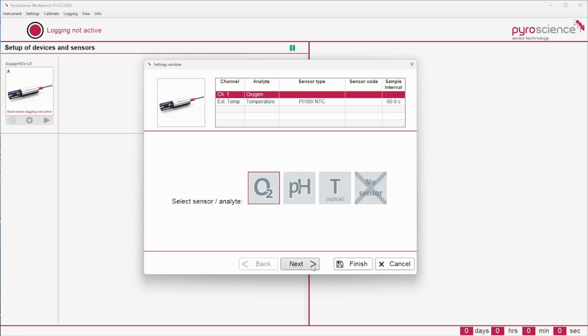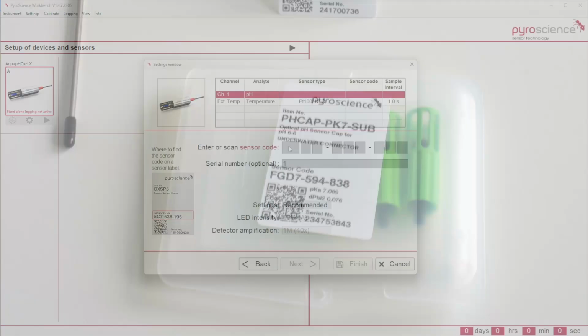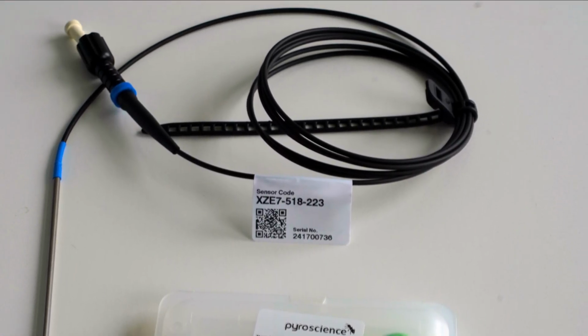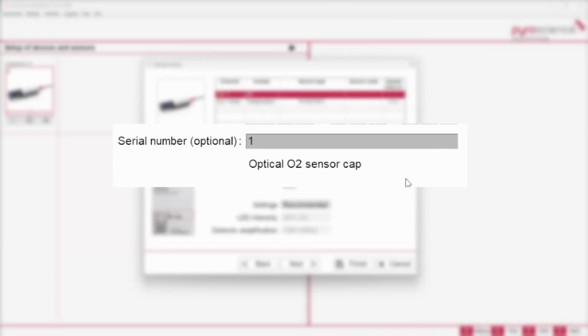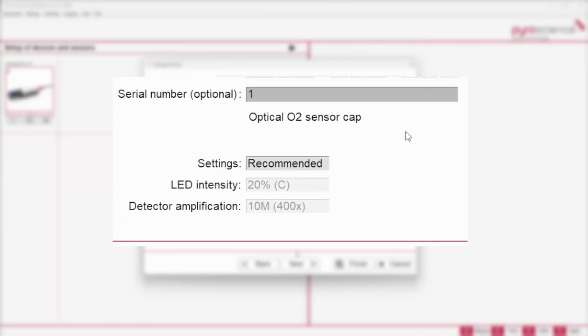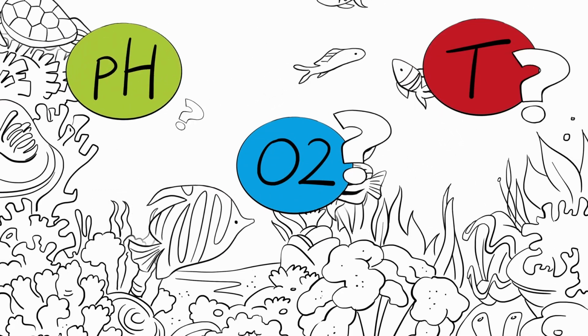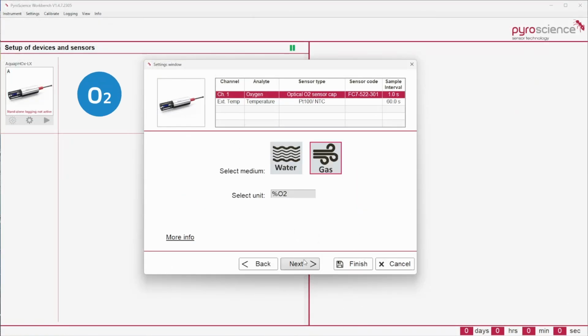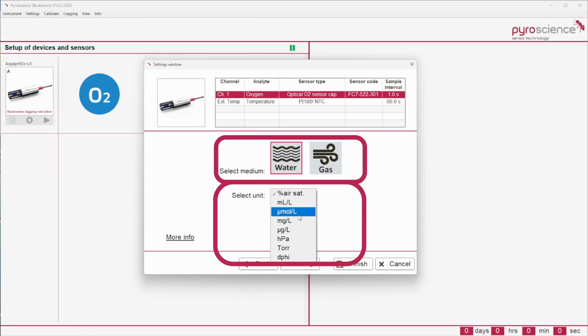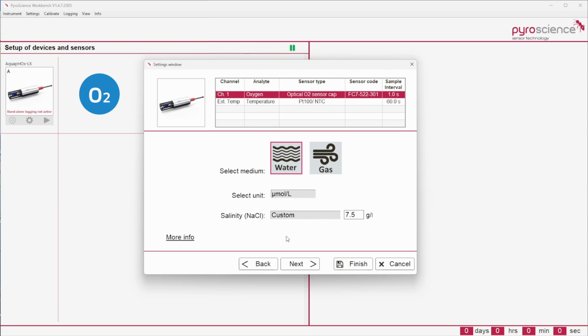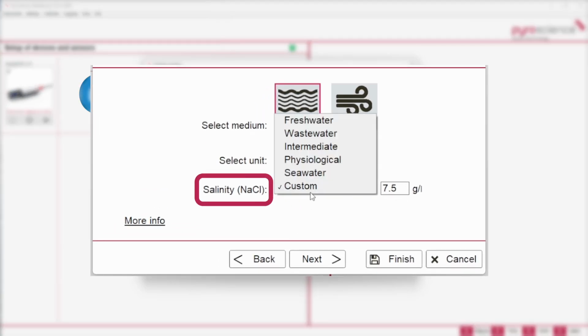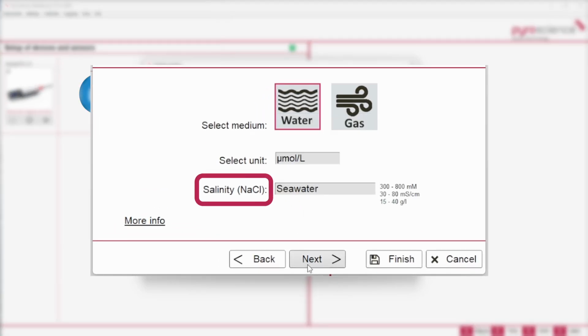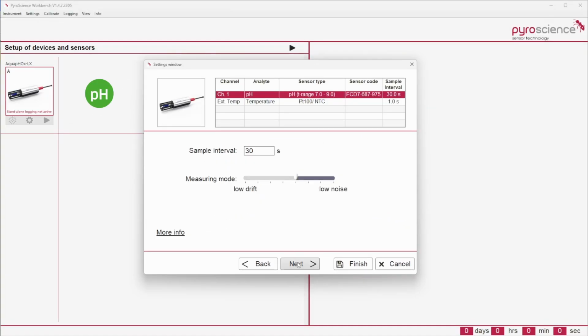Here, we demonstrate a new configuration. The software will ask you to enter the sensor code, which can be found on the package or on the cable of the sensor. Then enter the serial number and choose the recommended settings. Depending on the different analytes, several parameters need to be selected. Oxygen sensor settings will ask to select the medium and output unit first. For concentration units of the dissolved oxygen, you may have to enter the salinity of your sample based on sodium chloride concentration. The configuration of pH sensors will start with the sample interval.